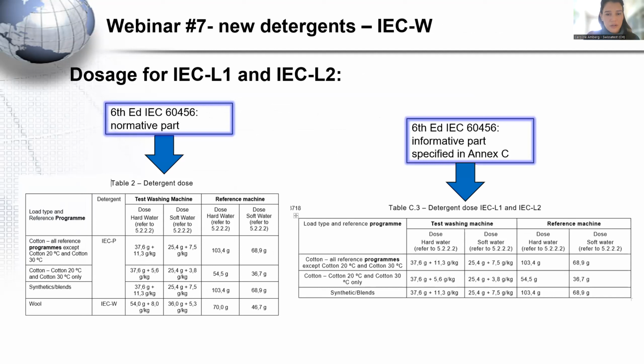Good. Then the dosage. On the left-hand side, you see the detergent dosage table for IEC-P and IEC-W. This is the normative part, whereas for the liquid detergents, the IEC-L1 and IEC-L2, the dosage is described in Annex C. And as you can see, the dosing or the amount is the same for the powder detergent and these L1 and L2s.